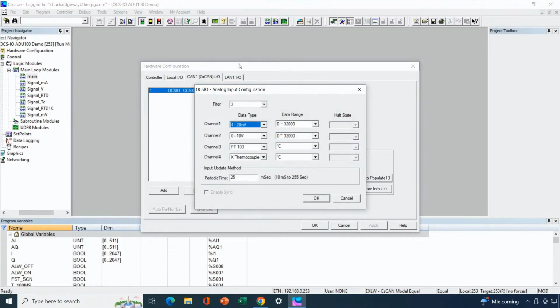So here are the different things that we can configure on a module by module basis. And that is, we have a filter, an analog filter, that can range from 0 to 7. The lower value of 0 actually is no filtering. And then as you increase up from 0, 1, 2, 3, all the way up to 7, you progressively get more stable readings that take longer to respond to changes. So it's a compromise between signal stability or reading stability and reading response time. So I like to start with 3 for most applications. It's a good middle ground.